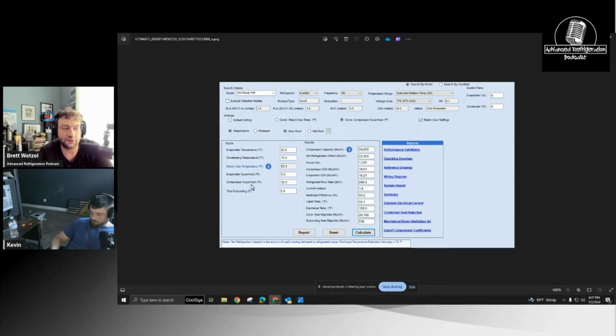But there's certain things you can do, like when it's on a rack, you can mitigate that a little bit. If it has a mechanical EPR, great. Then it's really a moot point because you control that all the time. But as we were stating before, if you have an electronic EPR and if they don't have some sort of max opening percentage on there, usually when the thing comes out of defrost, it'll open up 100%, driving that suction pressure to whatever rack it's on, and potentially oversizing the coil for a little bit and causing a really high superheat. And that's what a lot of times causes that feeding on the one side versus the other, like we explained. If the expansion valve isn't big enough, you're going to feed the path of least resistance, which once again is usually always that side where the pipes actually enter.